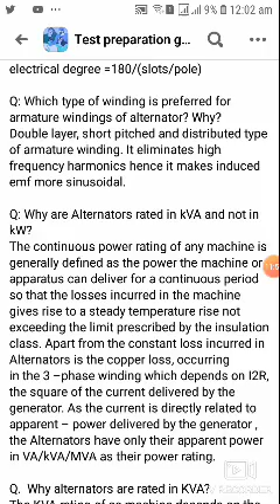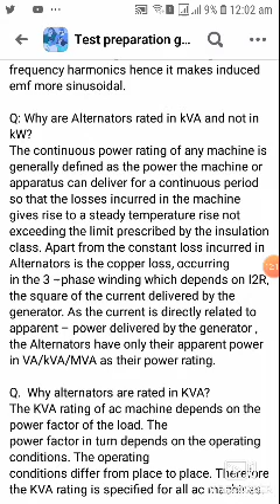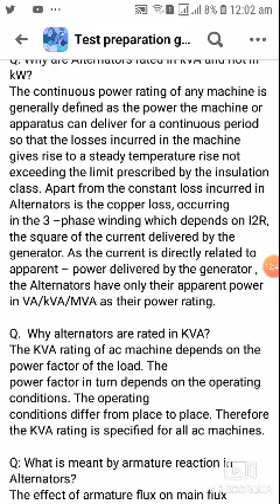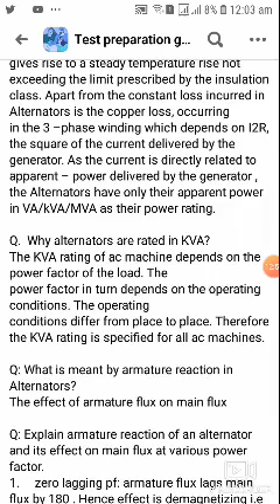Question number 25. Why are alternators rated in kVA and not in kW? The continuous power rating of any machine is generally defined as the power the machine can deliver for a continuous period, so that the losses incurred in the machine give rise to a steady temperature rise not exceeding the limit prescribed by the insulation class. Apart from the constant losses, the copper loss occurring in the three-phase winding depends on the I square R losses, the square of the current delivered by the generator, and the current is directly related to the apparent power delivered by the generator. The alternators have only their apparent power in VA, kVA, MVA as their power rating.